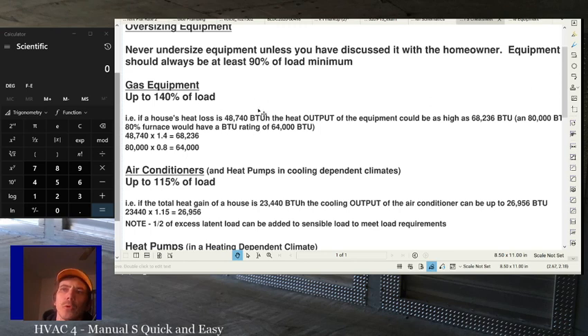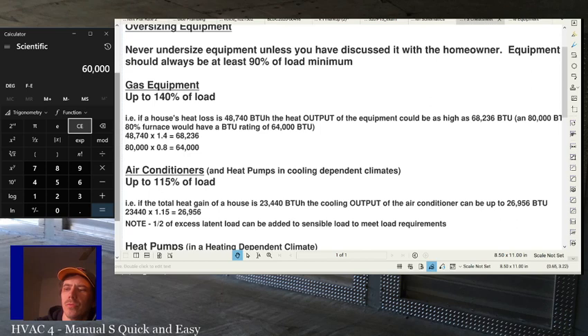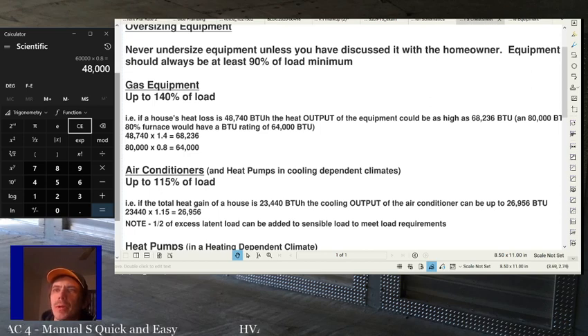So a house with a 48,740 BTU load, it is perfectly fine to use an 80,000 BTU furnace. A 100,000 BTU furnace would be too big. A 60,000 BTU furnace, actually let's do that math real quick. A 60,000 BTU furnace times 0.8 for 80% would be 48,000 BTUs. So it would actually be really close, right? A 60,000 BTU furnace would be pretty close, but an 80,000 BTU furnace in this case would probably be better.